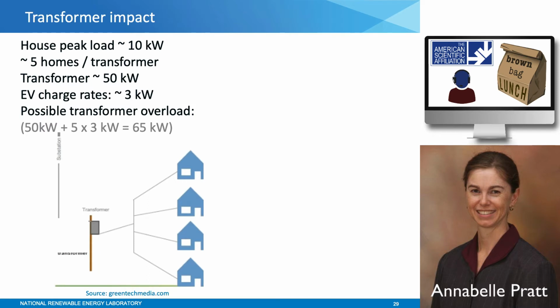One concern for the grid with electric vehicles is what happens if a lot of people, especially a lot of people on the same transformer, buy an electric vehicle. I have a drawing here that shows a transformer with 4 houses. Let's say you have a house peak load of about 10 kilowatts and you put 5 houses on a transformer - typically 5 to 8 homes on a transformer in the United States. So you'd want your transformer rated at roughly 50 kilowatts. If each homeowner bought a car with a typical charging rate of 3 kilowatts, you'd be adding 15 kilowatts - so there's potential for overloading the transformer.